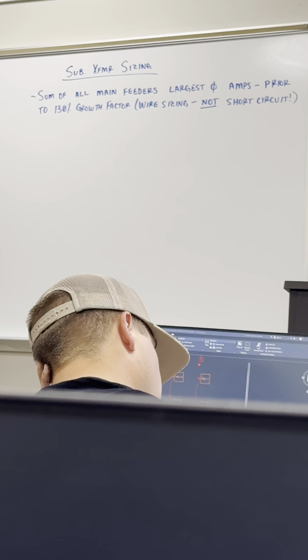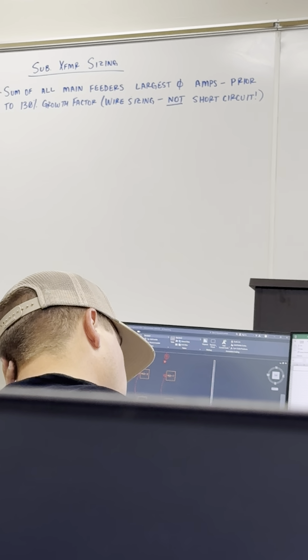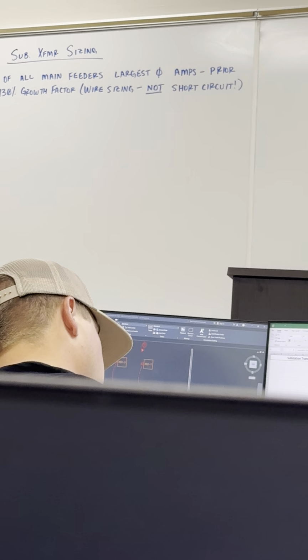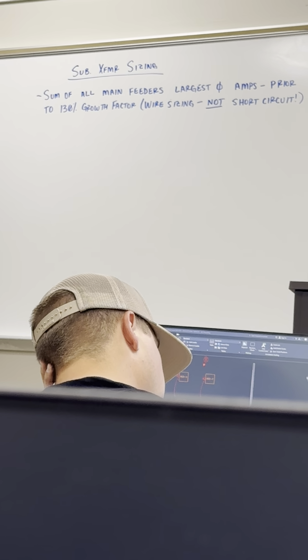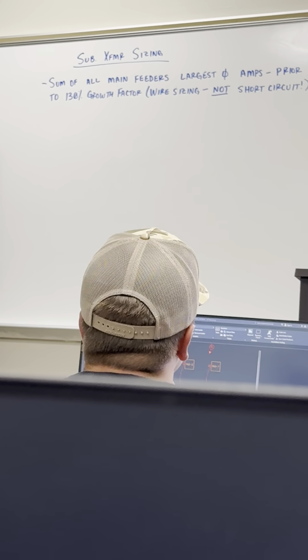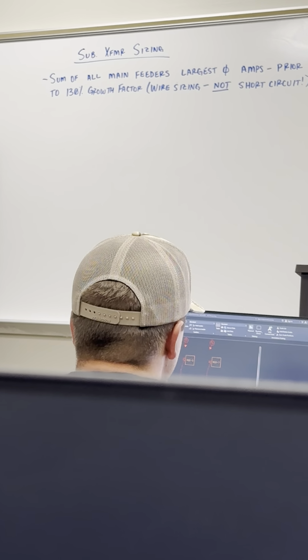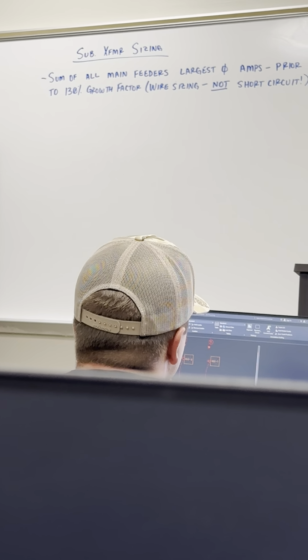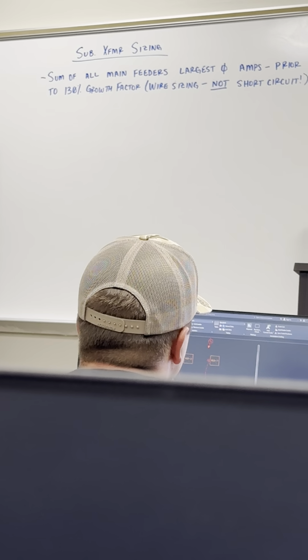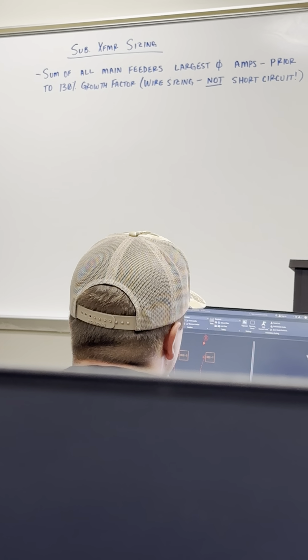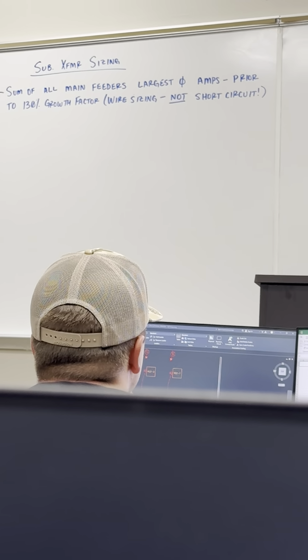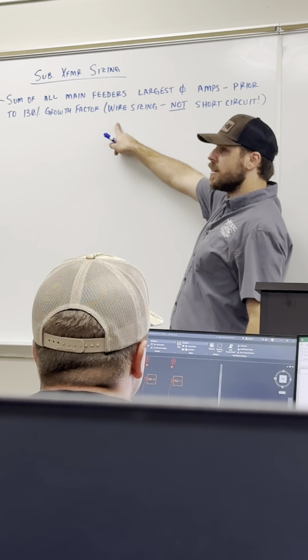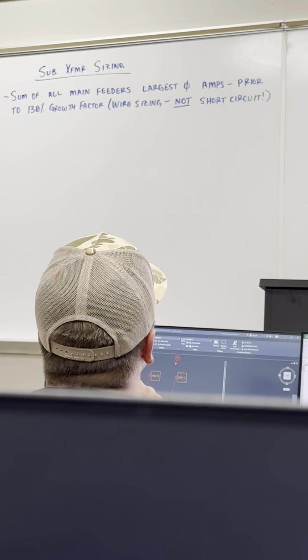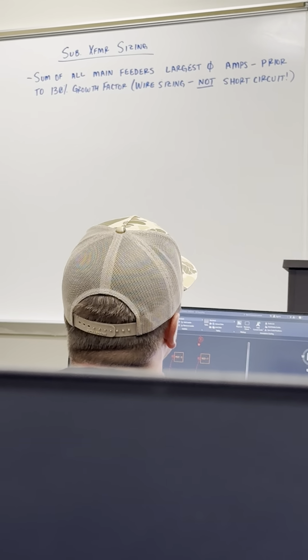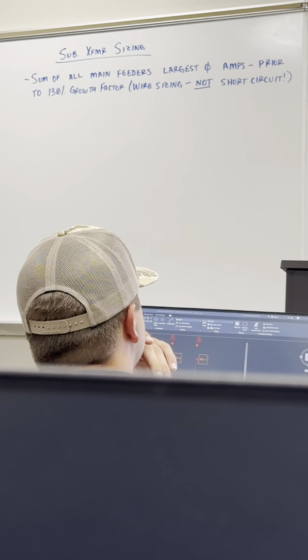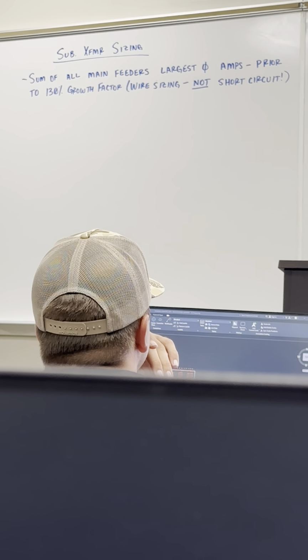You're going to take the largest phase, whether it was A, B, or C, off of each feeder prior to that 130% growth factor. So that means before. We added the growth factor over here, but we're taking these numbers here, before the growth factor. I put in parentheses that it dealt with wire sizing, not the short circuit protection sizing, right? We only added that growth factor on our wire sizing. We don't add a growth factor on a breaker.